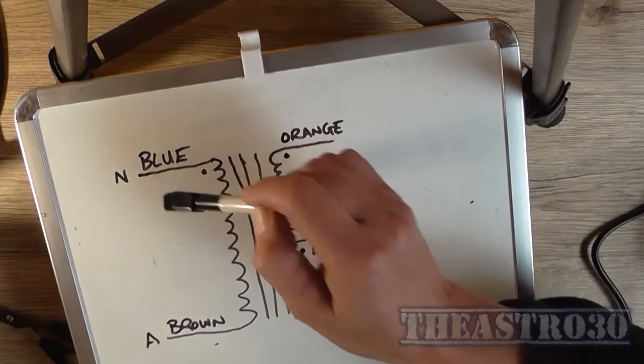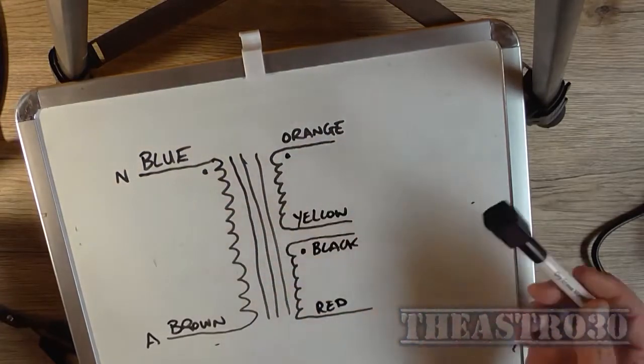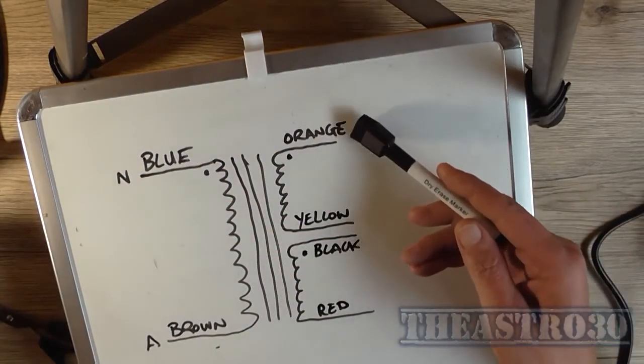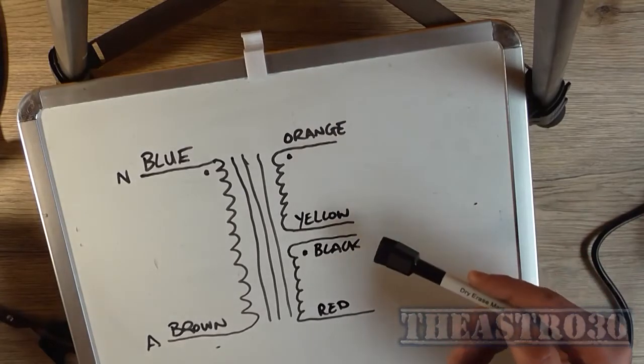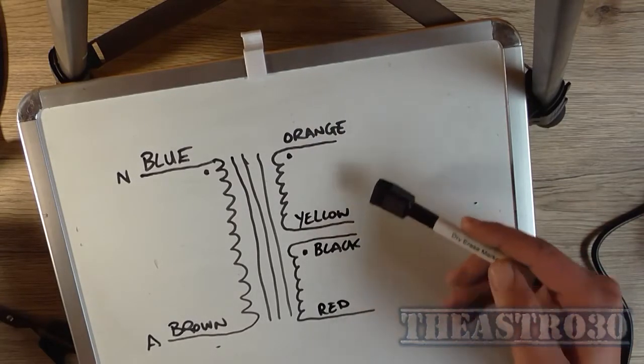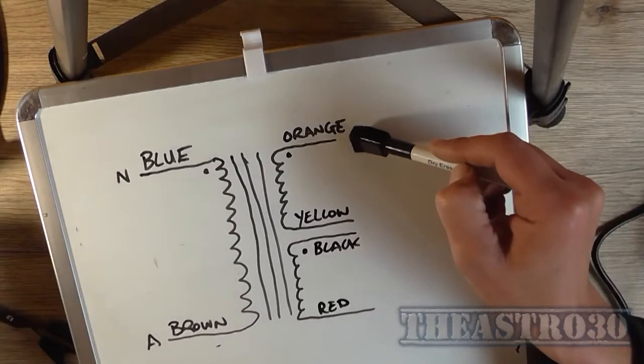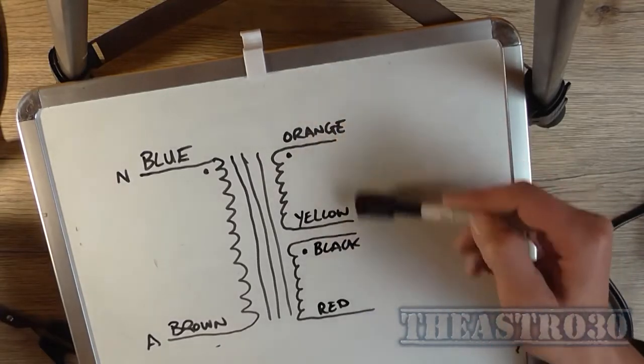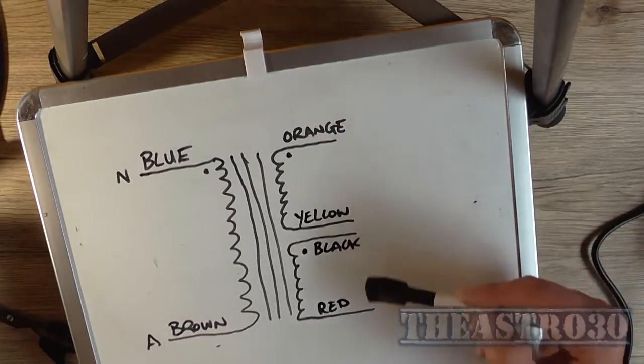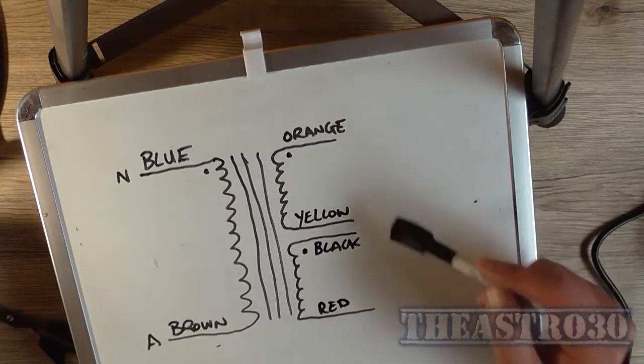So that dot relates to the neutral, that dot relates to the neutral. So basically we've got orange, which is one neutral, and black, which is the second neutral of the secondary. To keep them in phase, you join the black and the orange together. If you were putting these in parallel, the yellow and the reds are actually the secondary windings.